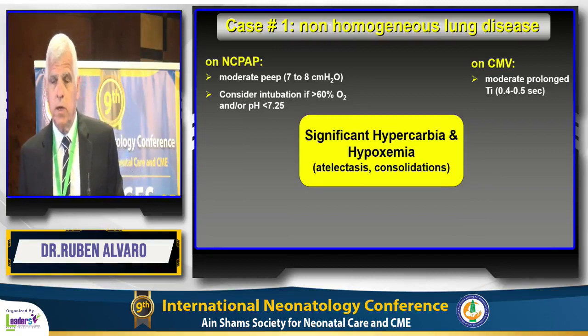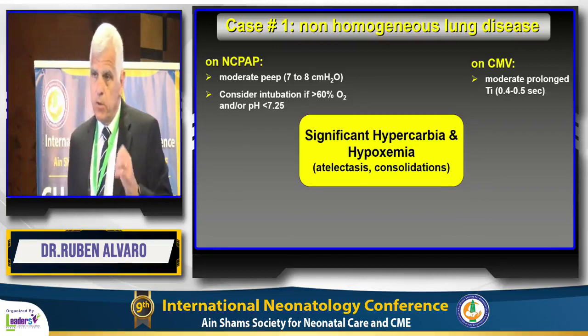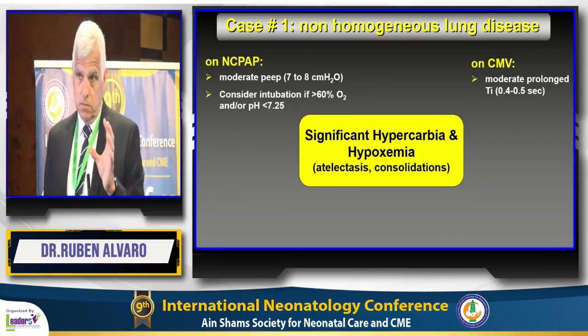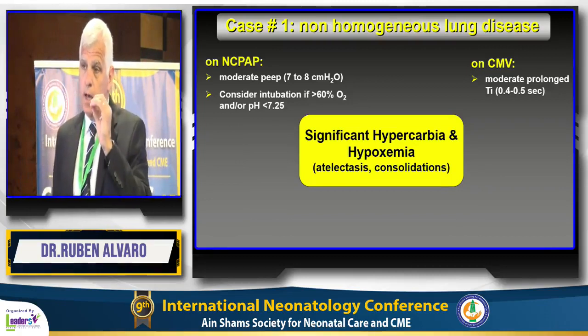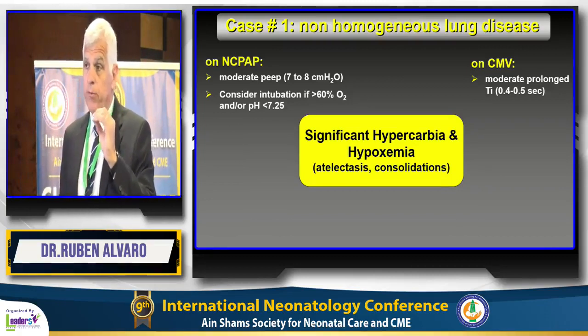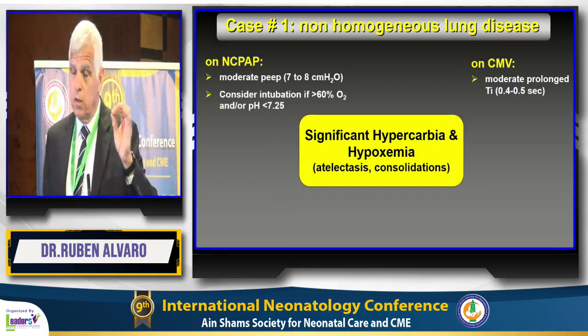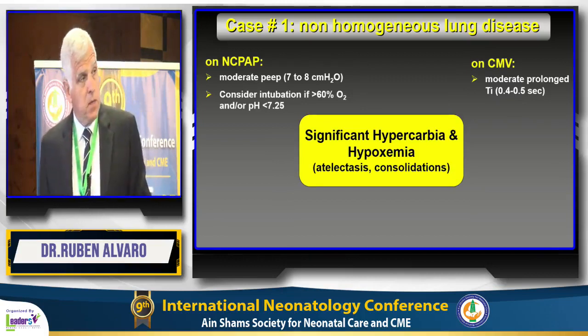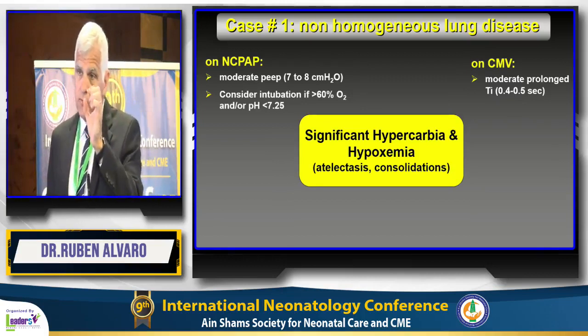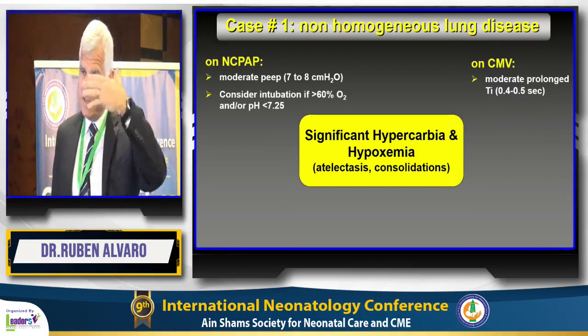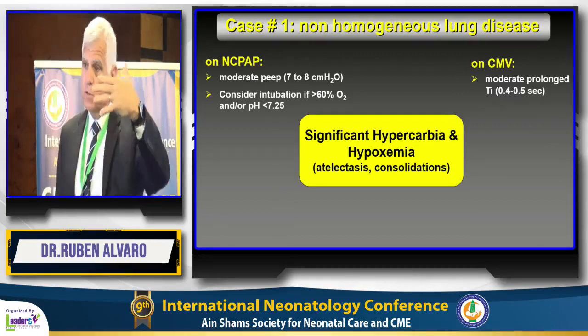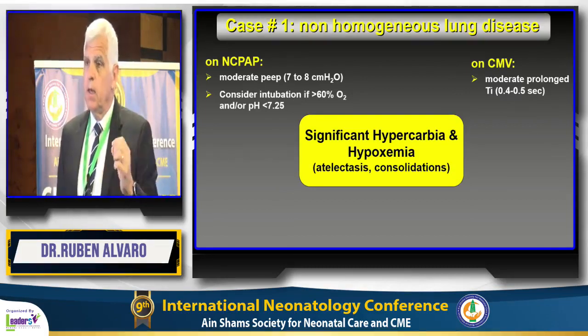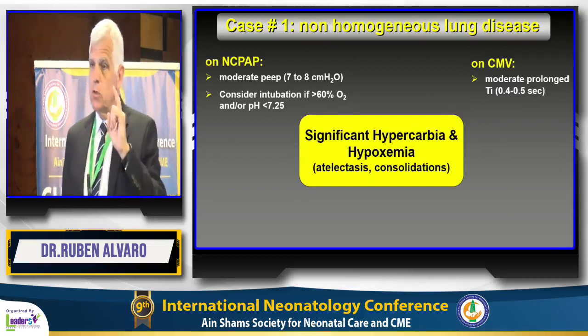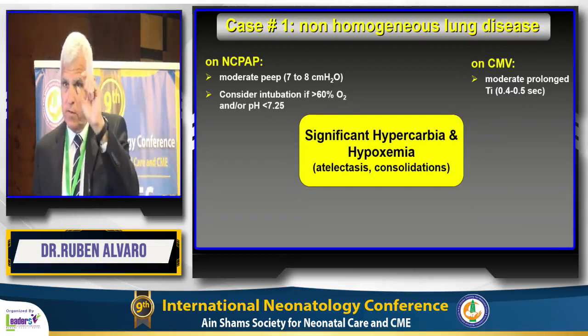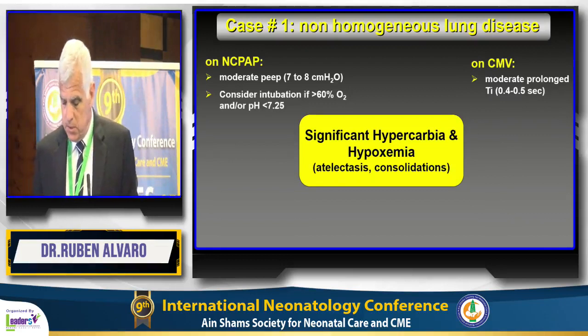You're dealing with a condition where the time constant is a bit too long, because you're dealing with most likely high airway resistance, if this is pneumonia or meconium aspiration. So your inspiratory time will have to be a bit longer to achieve full expansion of the alveoli. But look at your flow waveform to know if the inspiratory time you're using is the right length.